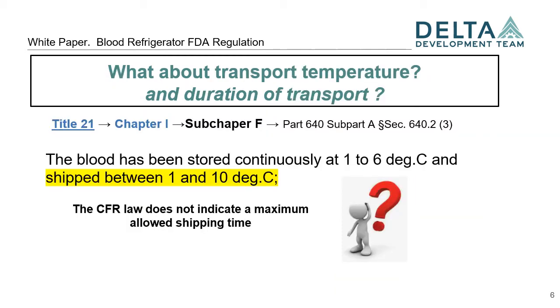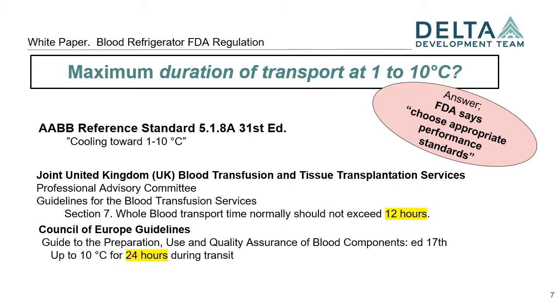Federal law dictates that the correct blood product storage temperature is maintained. Additionally, some allowance is given for some deviation during shipping or transport. Interestingly, no maximum allowed time at the higher shipping temperature is indicated. It is left to the transporter of the blood to select an appropriate standard to follow when preparing their own blood transport protocol. Generally, a maximum of 24 hours at 1 to 10C is considered appropriate.